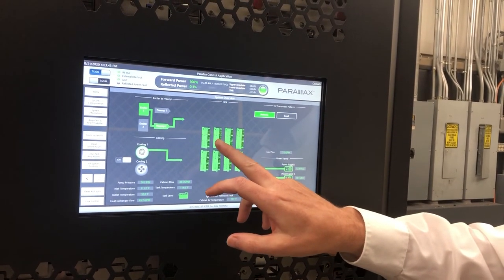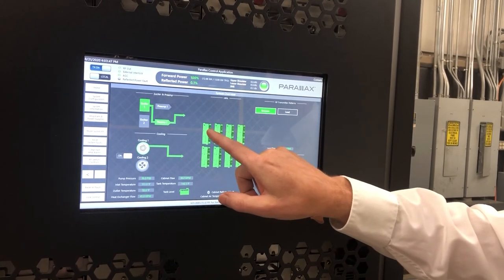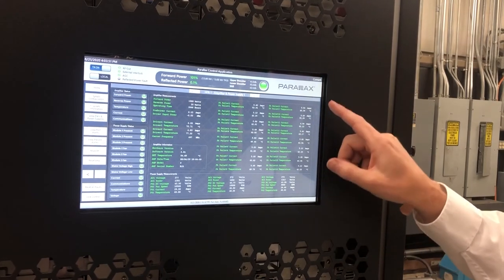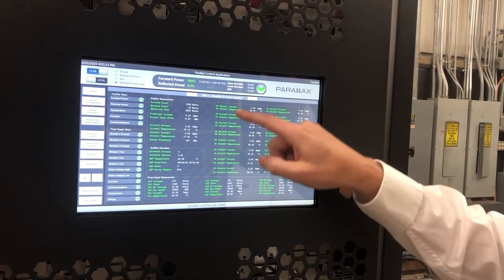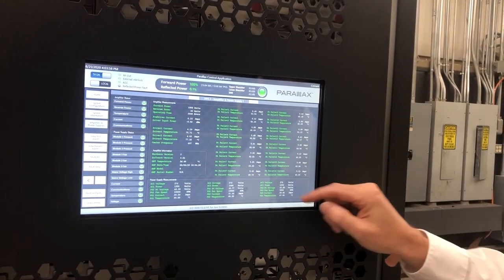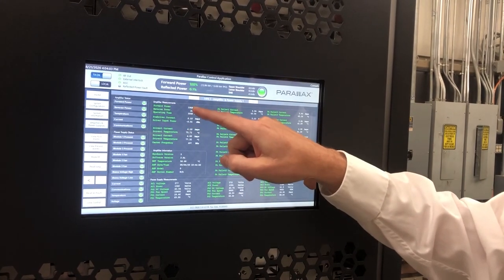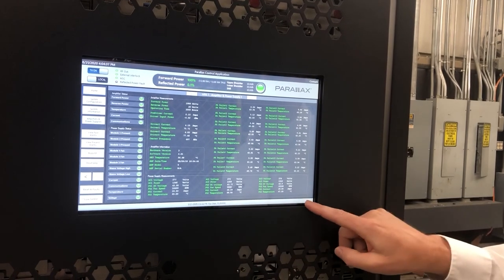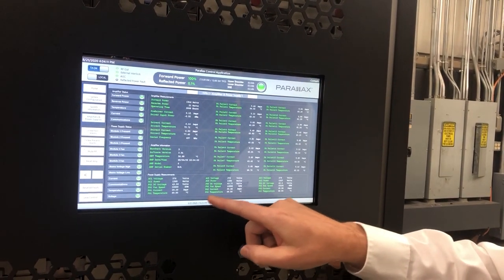The Parallax user interface has a lot of interesting information that you can dive down into to get exactly what's happening. If I click on one of the amplifiers, you can see the entire statistics of what's happening in that module. Here we have all 16 pallets — pallet current, pallet temperature, driver statistics, forward and reflective power. Down here we have amplifier information where we have AC voltage in, DC voltage out, fan speeds, temperatures, etc.